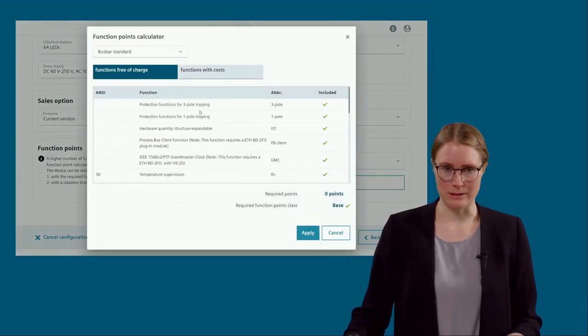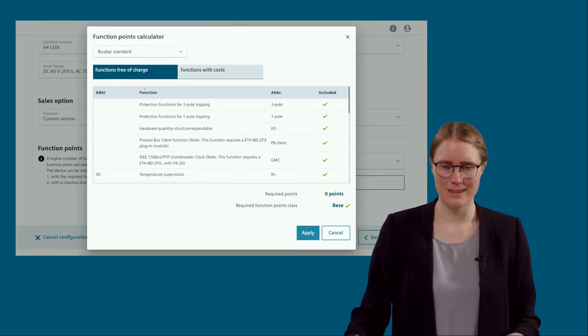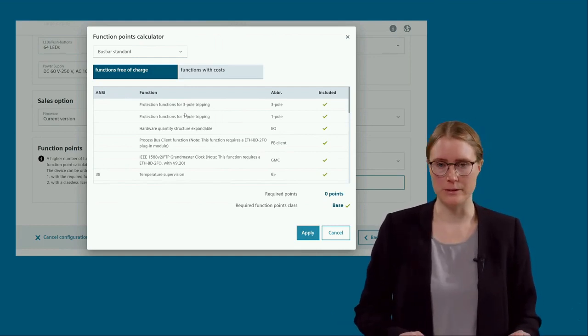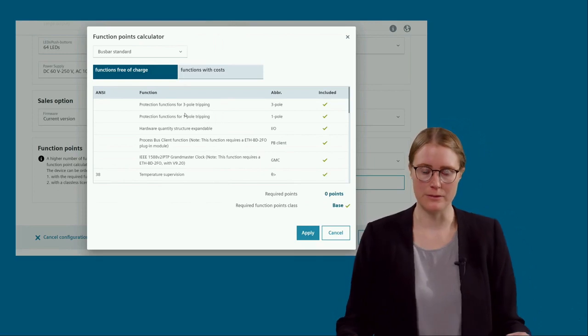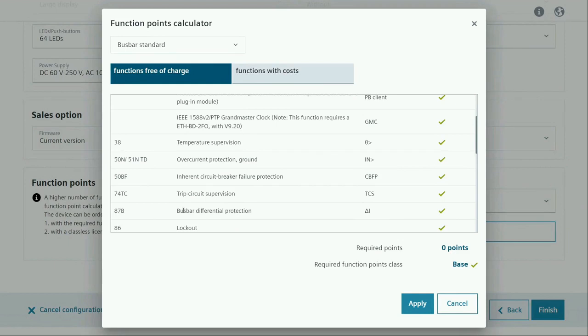Open this and we will have a quick look. So the first overview is the functions that are already included, where you don't need additional function points. For example, this is of course the busbar differential protection itself, because this is the main protection function, and this is of course included. You also have the inherent circuit breaker failure protection, which Rainer mentioned earlier. This is also always included in this setup.